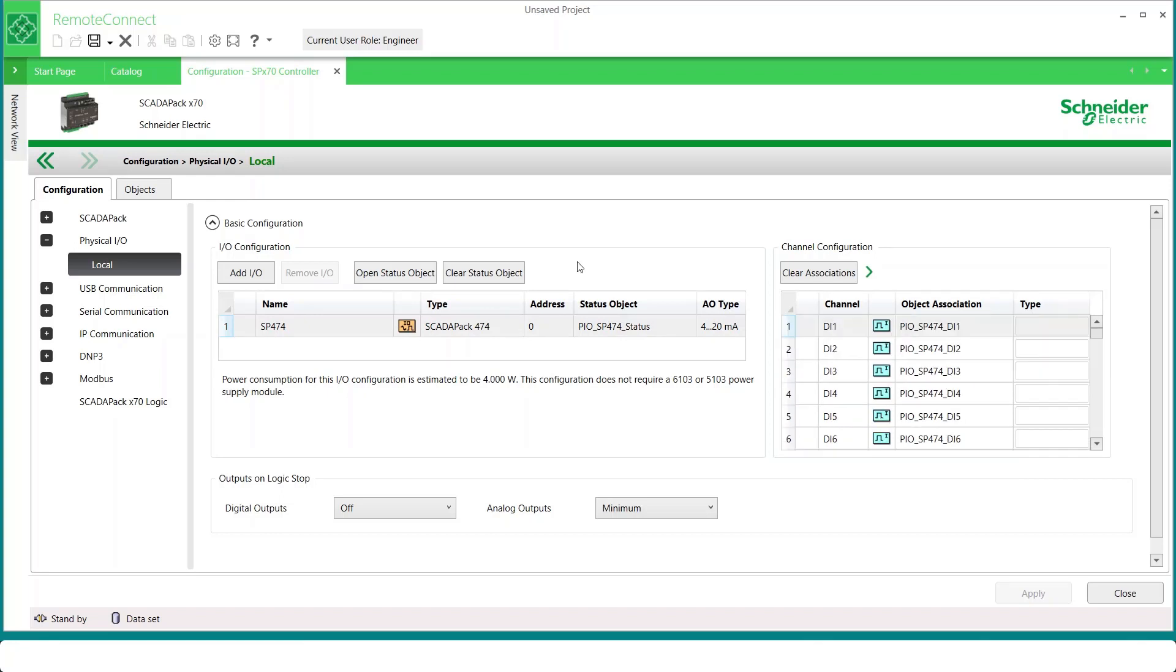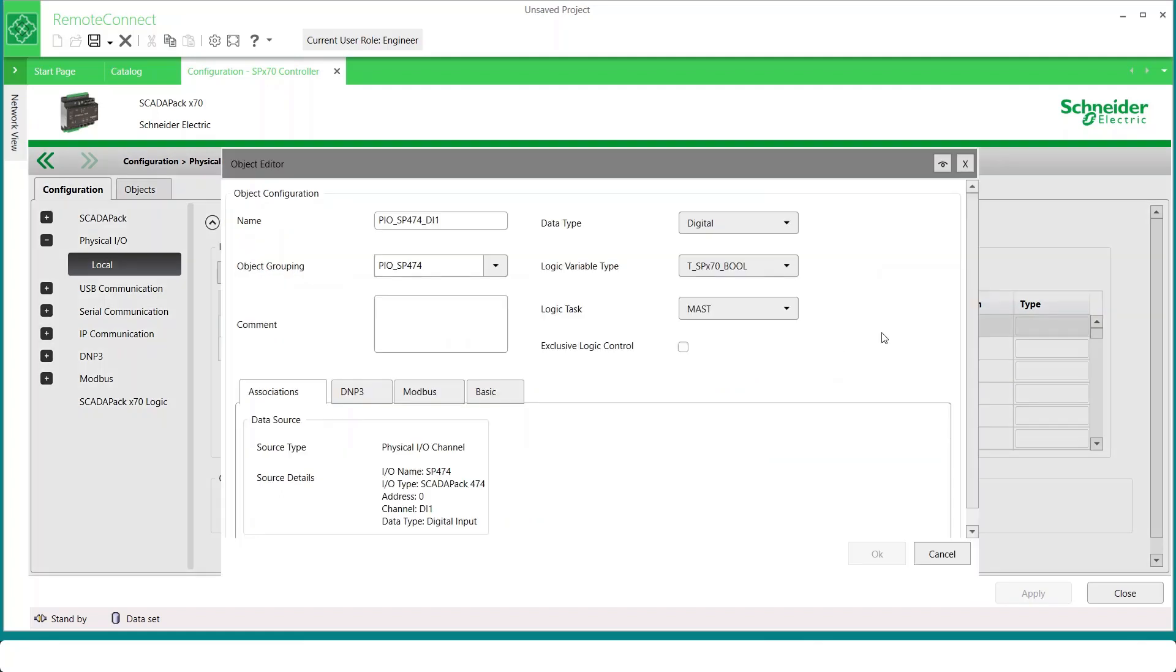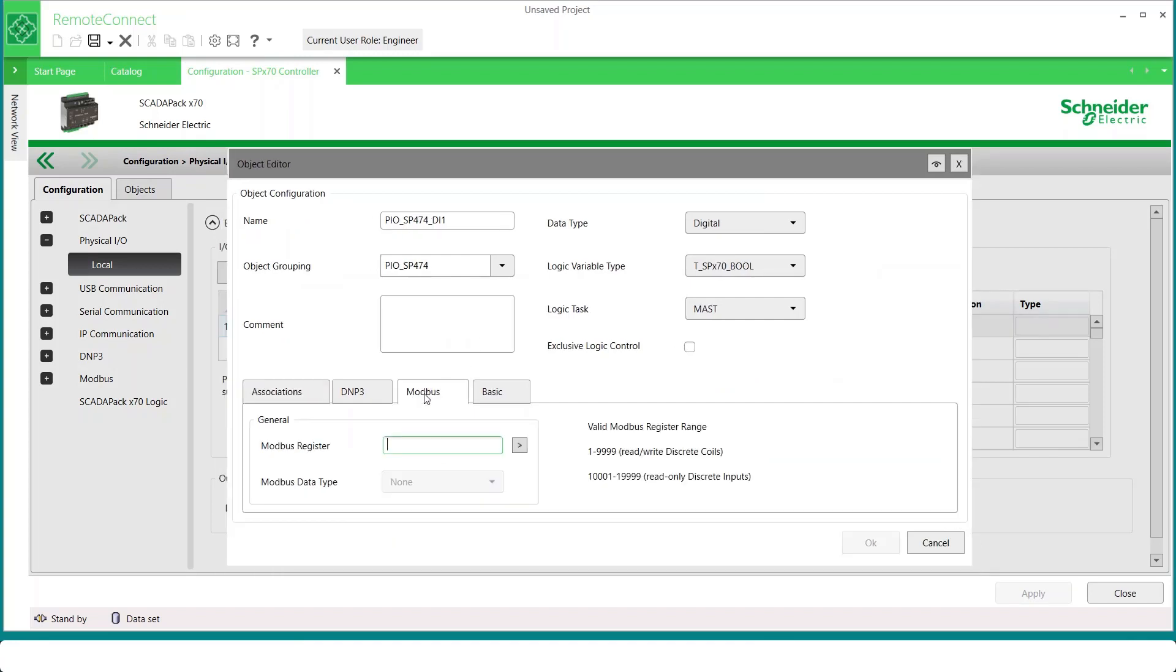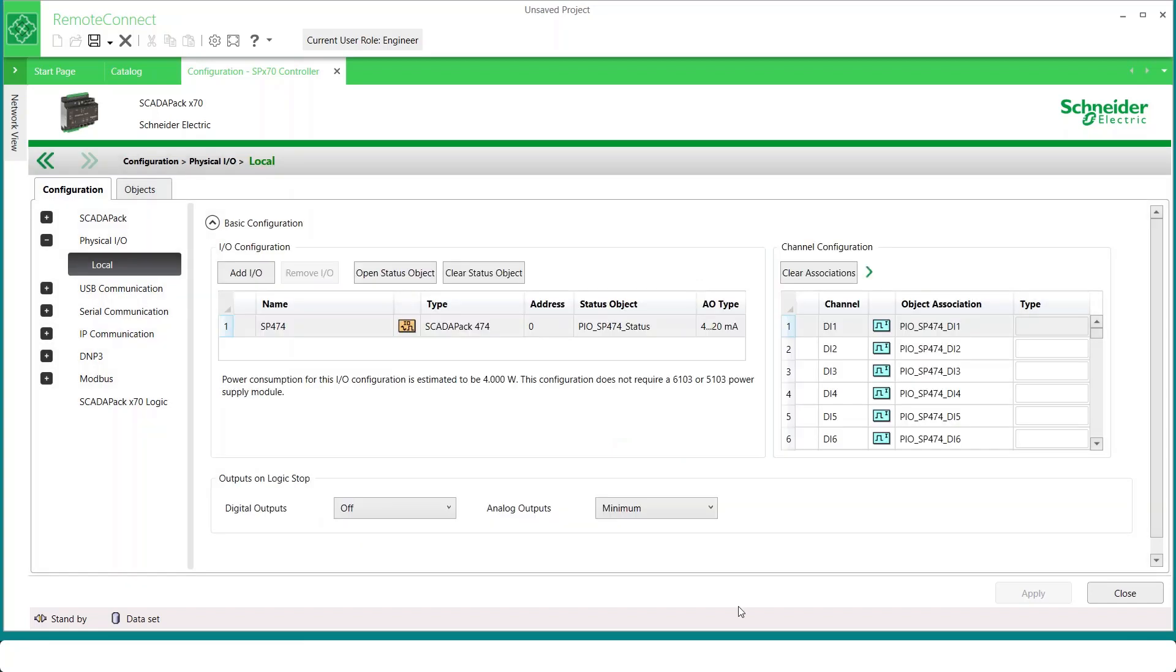You can double-click on any channel shown here, and then change its name if desired. Assign it a Modbus or DNP3 point number. Make other configuration changes as well. You can assign it to a logical group, which allows related objects to more easily be monitored in an object browser. Or you may prefer to edit these while on the Objects tab, where all objects are displayed both physical and internal. We'll look at that shortly.